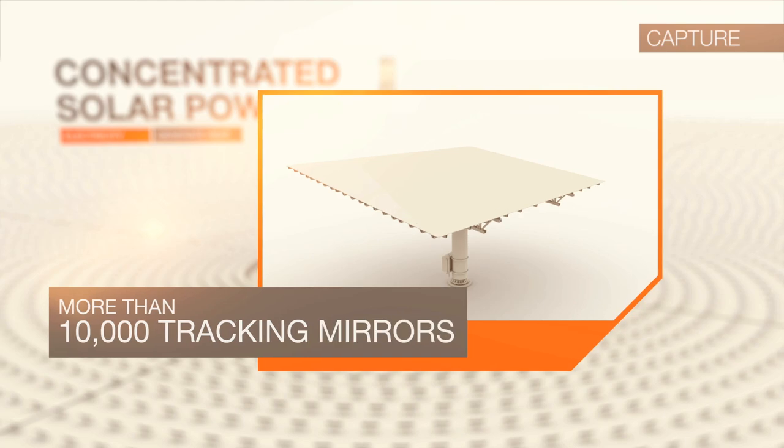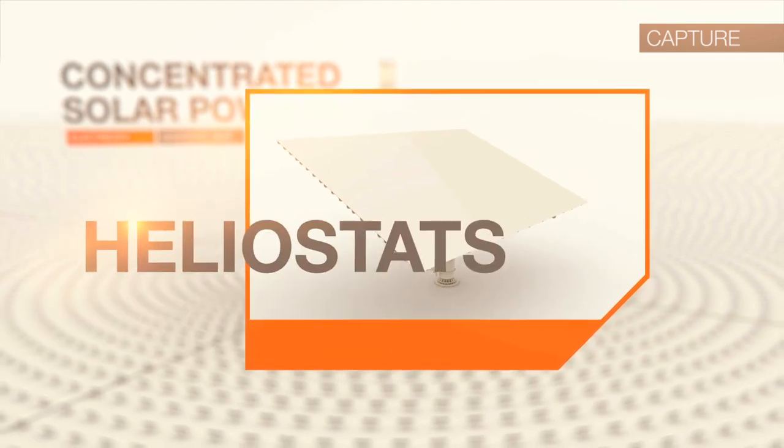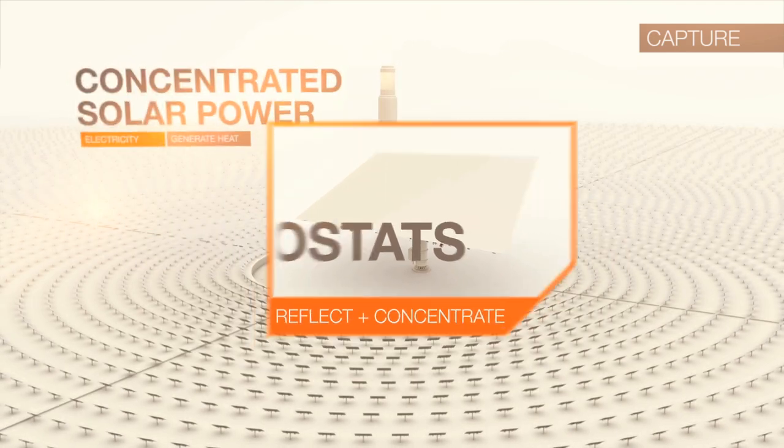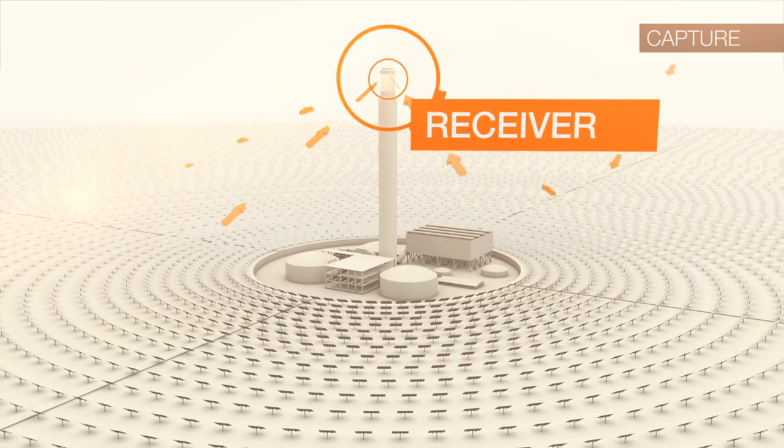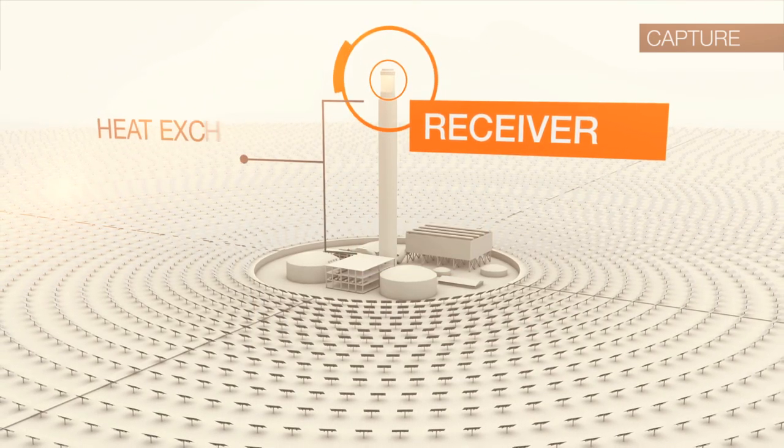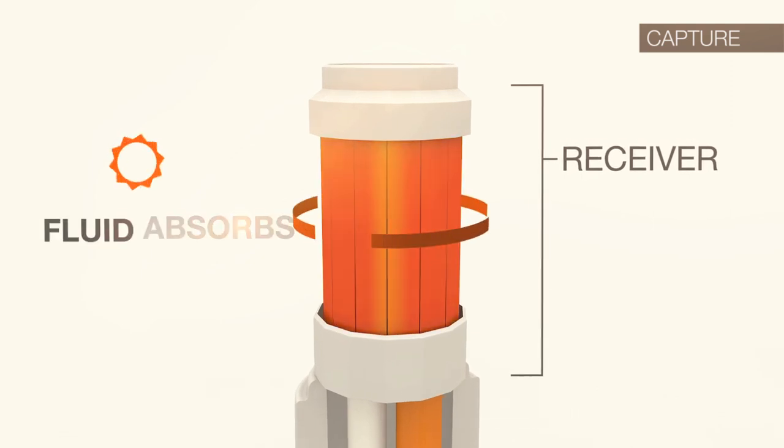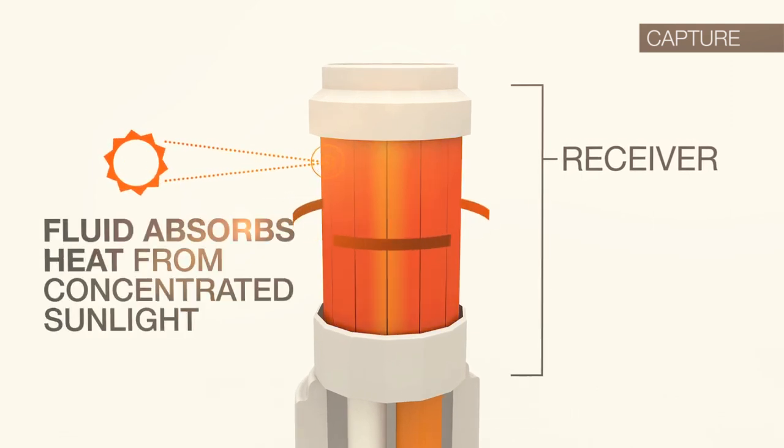More than 10,000 tracking mirrors called heliostats reside in a four square mile field where they reflect and concentrate sunlight onto a large heat exchanger called a receiver that sits atop a 550-foot tower. Within the receiver, fluid flows through the piping that forms the external walls. This fluid absorbs the heat from the concentrated sunlight.